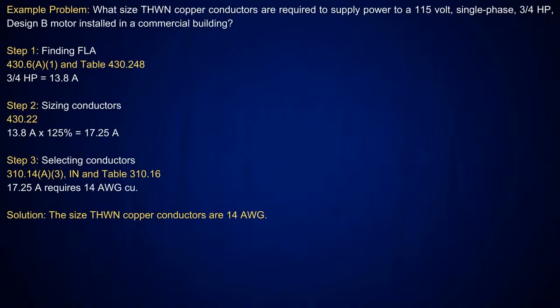Anytime I'm sizing my overcurrent devices and my conductors, I'll use one of the tables that's listed in tables 430.247 through 250. Okay? So in this case, I'm going to size conductors here, and I have a 115 volt single phase, 3/4 HP design B motor. Well, since it's single phase, everybody should get used to this. If it's single phase, you're looking at table 430.248, and if I'm doing 3-phase, I'm looking at table 430.250 to get my amperage ratings. So basically what I'm trying to tell you here is I'm going to use the amperage rating that's in the tables. Now, when I get over to AC units and refrigeration circuits, then you're going to use the nameplate. Okay? Right.